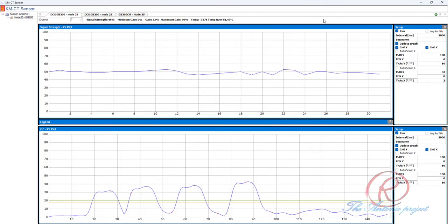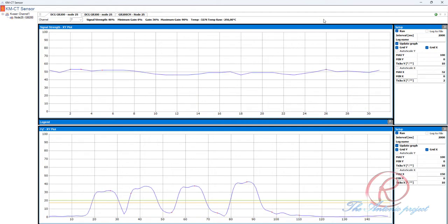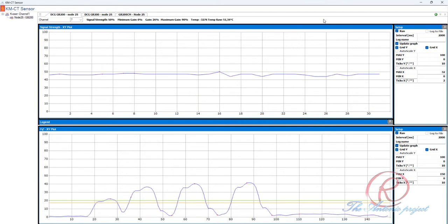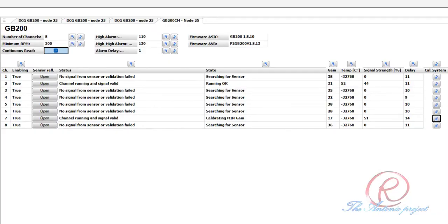Considering this state and the signal strength, which is sometimes zero or lost, there is a high possibility that the sensor is malfunctioning. Other possibilities are poor cable connections in the SPU or cable gland. Following is the calibration of the big end bearing temperature sensors, conducted on all the sensors with the engine stopped.